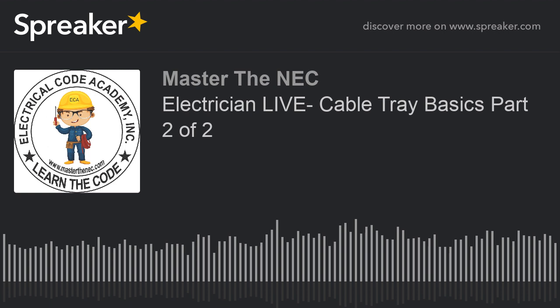And then it says to use 392.80(A)(2) for single conductor cables. And we did that just a second ago. So far it's looking like we treat each set separately: the multiconductor cable ampacities in accordance with 392.80(A)(1), and the single conductor cables in accordance with 392.80(A)(2). That sounds real simple so far. Just forget that the other one exists and do your calculations based on this one. So far it seems pretty simple.